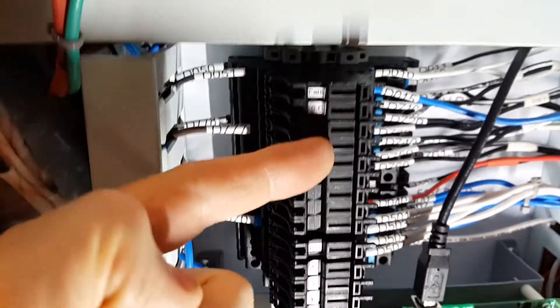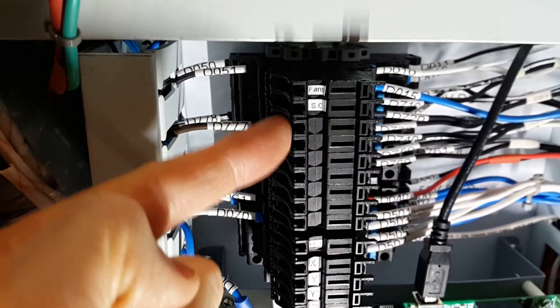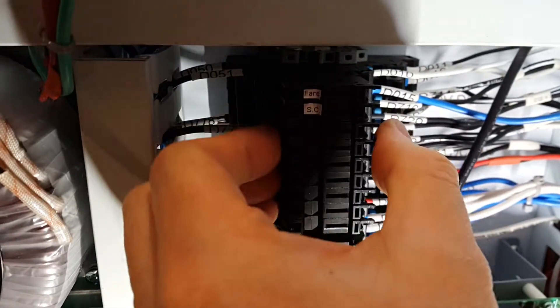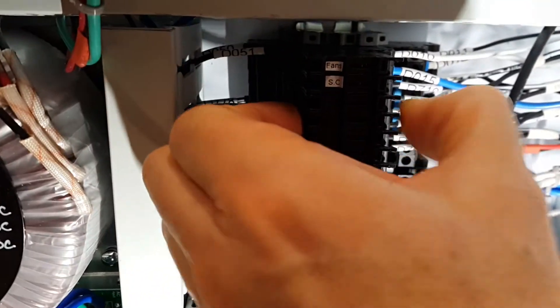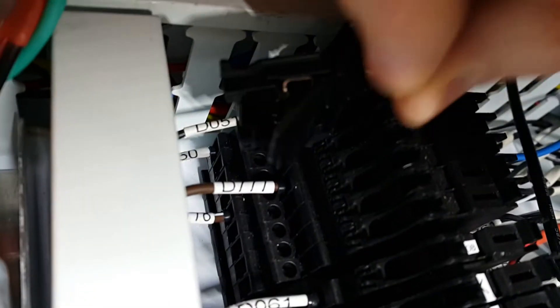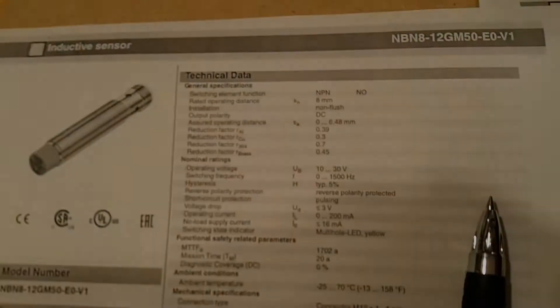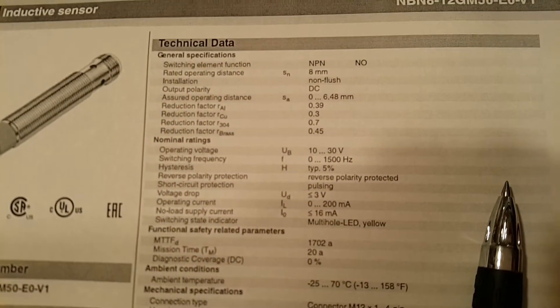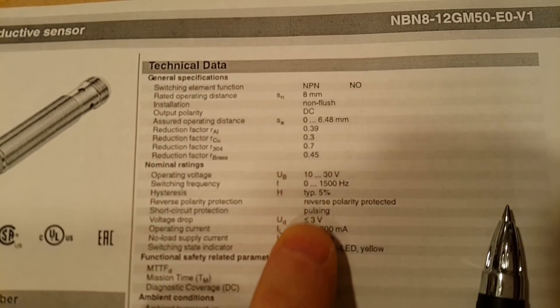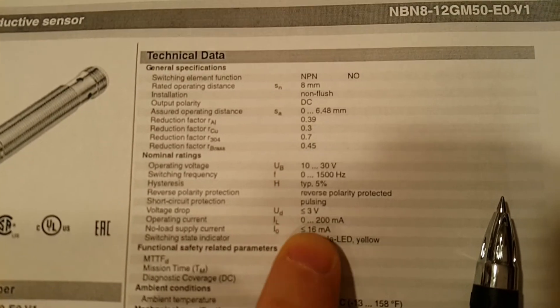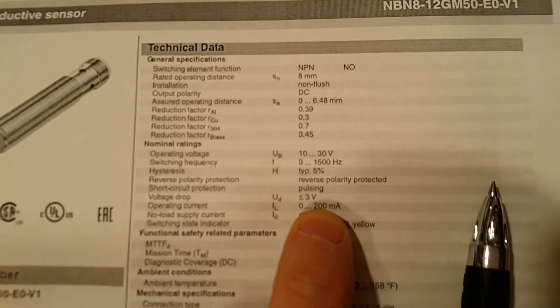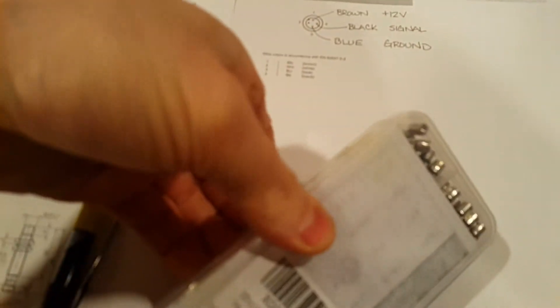Each one of the proximity sensors is going to be individually fused here. If we open up one, you can see the fuse holder is empty. Come back to the spec sheet, we see that the operating current is zero to 200 milliamps. I have my little fuse kit here. These are five by 20 millimeter fuses.